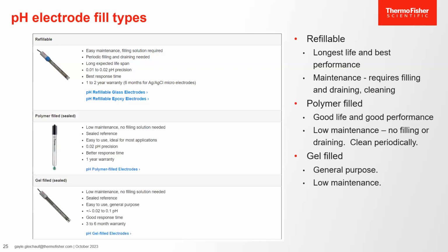Low maintenance electrodes are filled with either a solid polymer or a gel fill. Low maintenance electrodes don't require topping up or draining and refilling the electrode fill solution. They're convenient to use and only require periodic cleaning. Typically, they do not last as long as refillable electrodes.